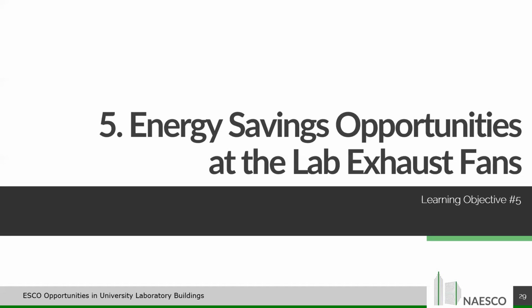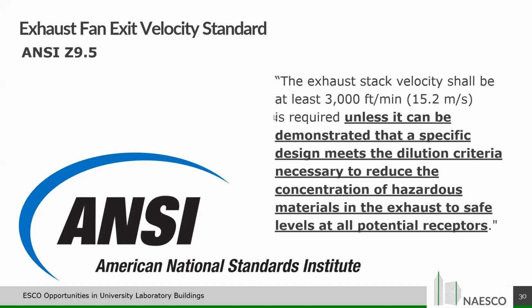All right, so Bill took us through energy saving opportunities inside the lab, but what about the lab exhaust fans? What can we do there? Well, I'm back to ANSI Z9.5. We talked about the actual code requirement. This is the code stated in a little more detail. Exhaust stack velocity shall be at least 3,000 feet per minute unless it can be demonstrated that a specific design meets the dilution criteria necessary to reduce the concentration of hazardous materials in the exhaust to safe levels at all potential receptors. Until recently, no one was taking advantage of this.